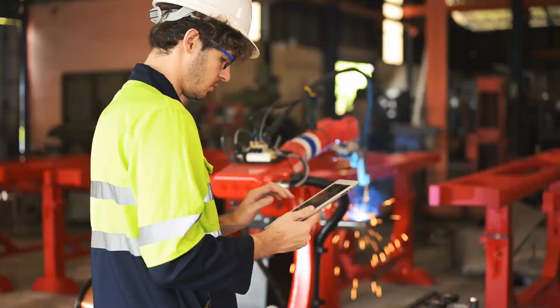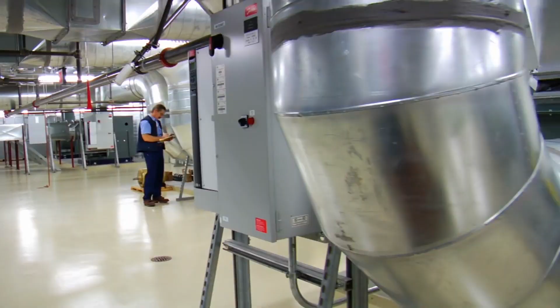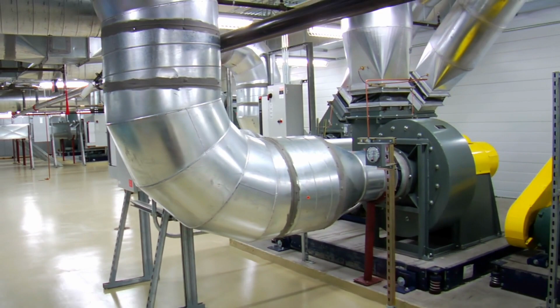Flushing and cleaning of pipes needs to take place, verification of P&ID drawings needs to be done, point-to-point and megger checks are required, and loop checks need to be completed. There is a standard set of important pre-commissioning activities that need to be performed for all industrial plant processes to prepare equipment for more detailed system commissioning.